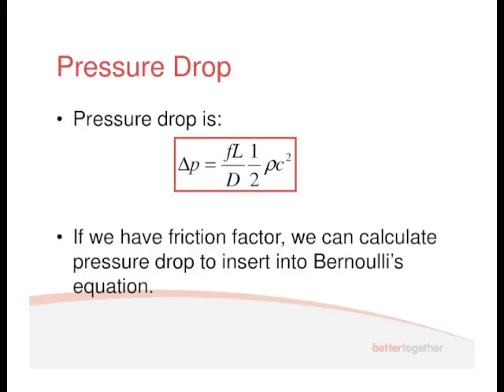We covered turbulent flow last week and came up with the equation for pressure drop as the friction factor times the length divided by the diameter times the dynamic pressure. Generally length and diameter we know, and we also tend to know the flow rate so we can work out the velocity C. But this F term — the friction factor — is the thing we have to work out.